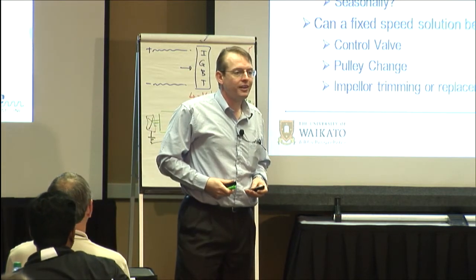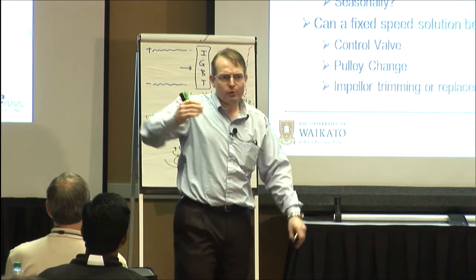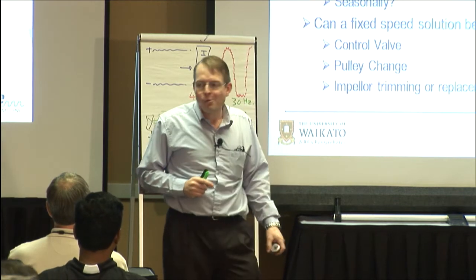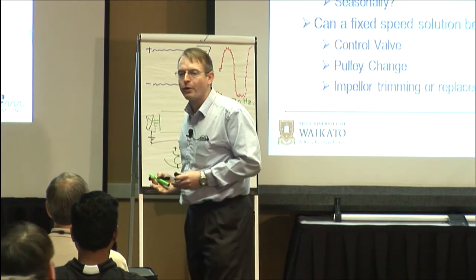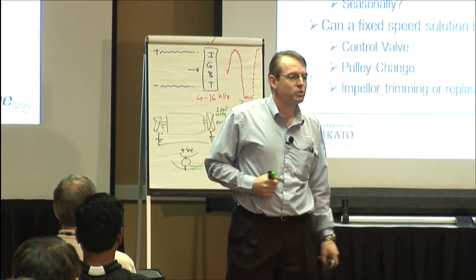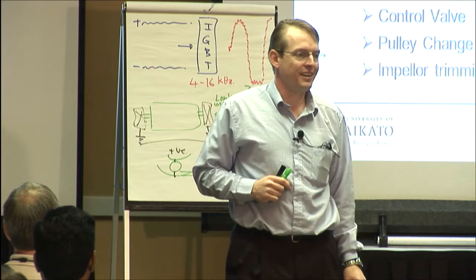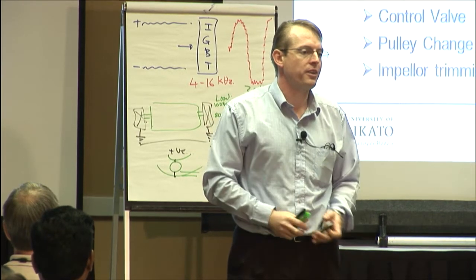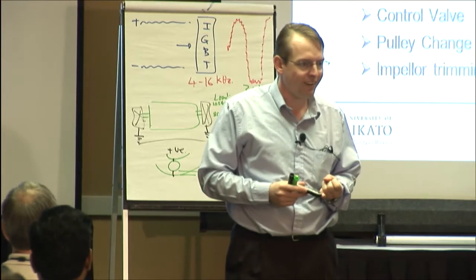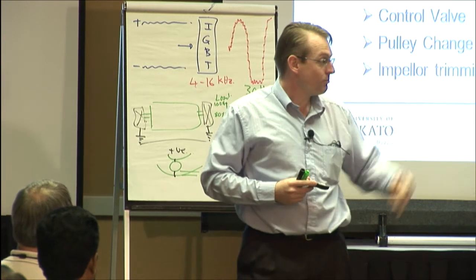So what does he do? Goes an extra size, throws the VSD on and says, that's all right, we'll just tune it on commissioning and leave it. I've seen so many VSD-driven pieces of equipment where the VSD's been just set from the day it was commissioned and has run continuously at that speed from then on. You're just burning 3% for nothing, plus you've got an additional asset that you've got to then keep a spare for, okay, and additional failure modes.